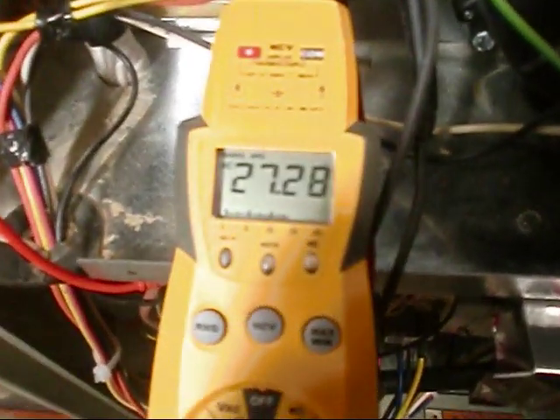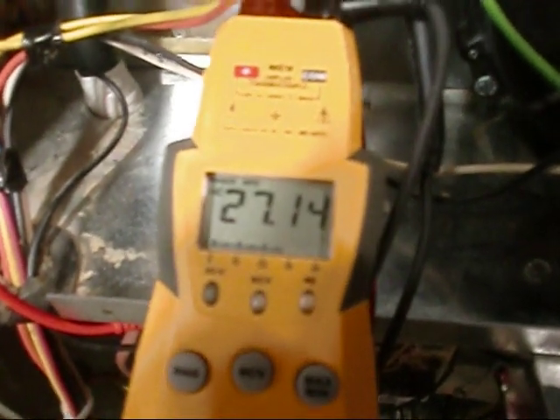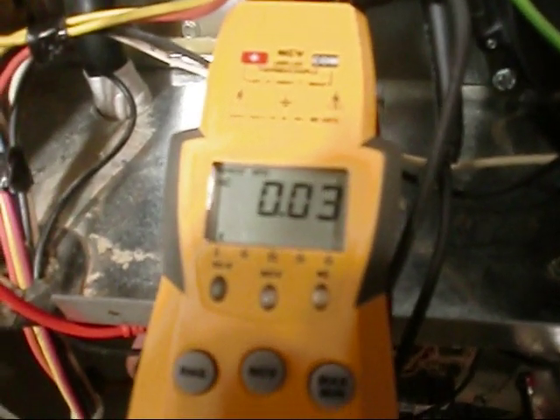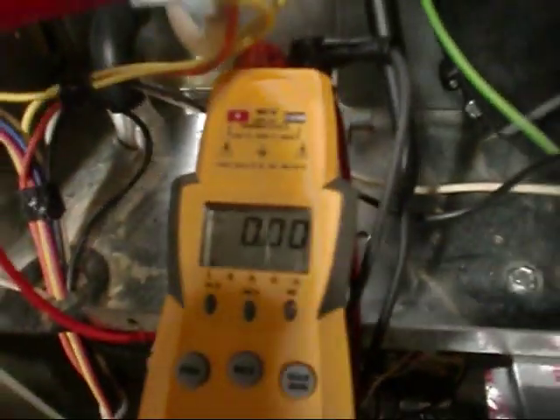And once that pressure switch closes, it should go back to 0.001 or something like that. And it's going to look like there's no power going to it. However, let's take a peek here. Boom, 24, 27 volts, same thing, low voltage. As soon as that, see, that's how fast that thing is. Boom, she's out.